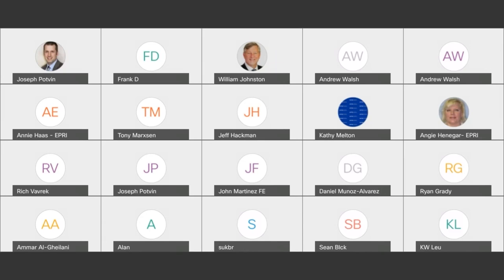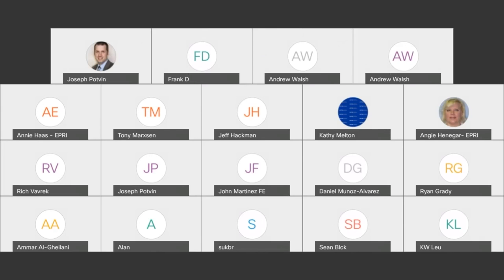Okay, I'll run through some of the ones I see in the chat. Someone asked about splices and detecting splice failures. The answer is yes, we have detected them, and we're actually monitoring a number of splices in Australia and the US to see what the risk is when we pick up a splice that looks bad. But visibly, when you inspect it, there's absolutely no difference between it and every other splice in the neighborhood that doesn't show up on our system. This coming summer fire season in Victoria, we'll be replacing a number of splices, or our customers will be replacing them, before the fire season based on the EFD results.